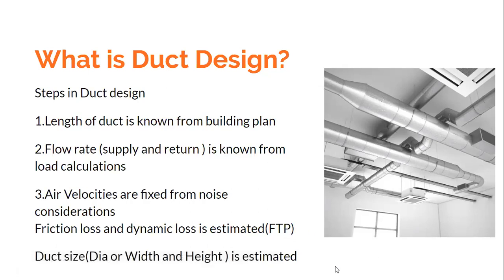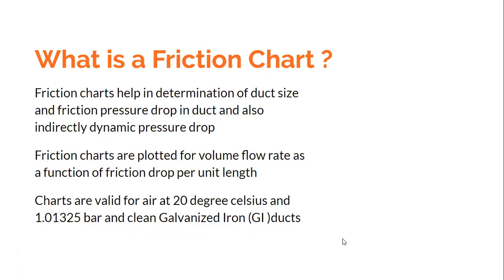Once you get the friction loss and dynamic loss, you can estimate the Fan Total Pressure (FTP) and hence select the fan. These are the important steps of duct design. The outcome of duct design is generally that we find the diameter or the equivalent diameter of the duct.